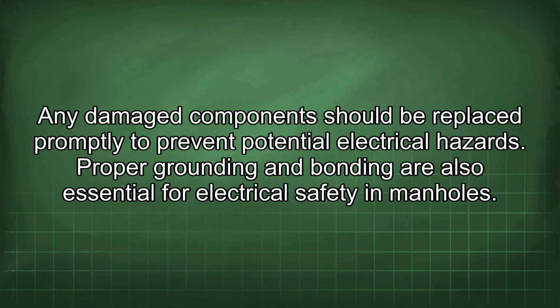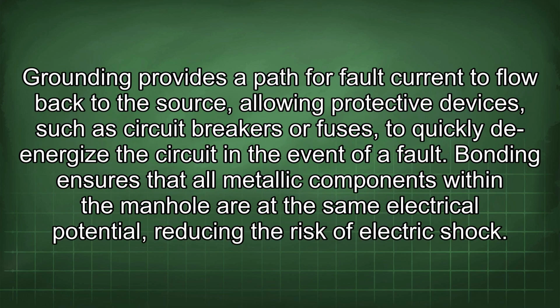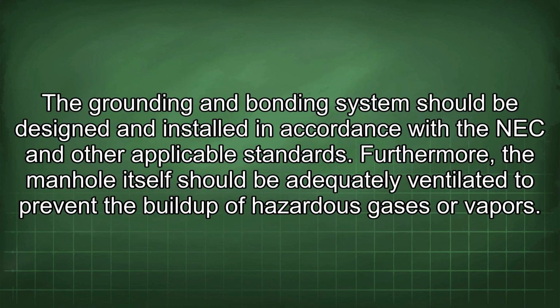Proper grounding and bonding are also essential for electrical safety in manholes. Grounding provides a path for fault current to flow back to the source, allowing protective devices, such as circuit breakers or fuses, to quickly de-energize the circuit in the event of a fault. Bonding ensures that all metallic components within the manhole are at the same electrical potential, reducing the risk of electric shock. The grounding and bonding system should be designed and installed in accordance with the NEC and other applicable standards.